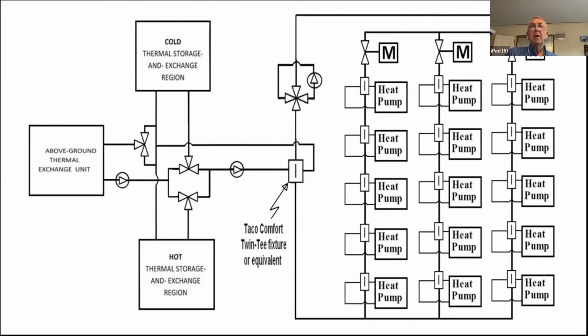And if you look at the valve arrangement on the left, you'll see it's identical to what we've been discussing. These are switched around so that the above ground unit is now on the far left rather than at the bottom. But the two valves and the two water pumps and the 3 valves are just identical to what we had in the previous design.